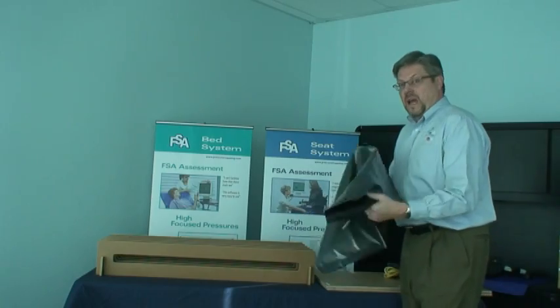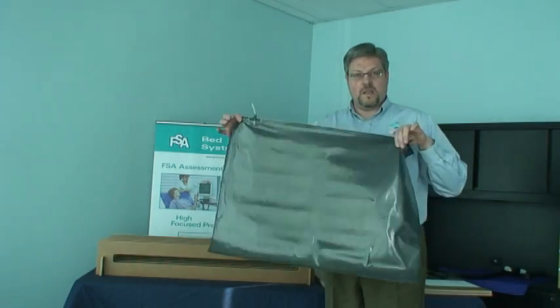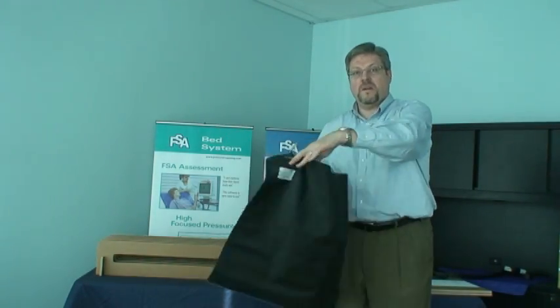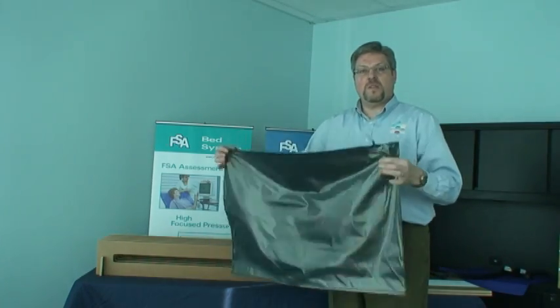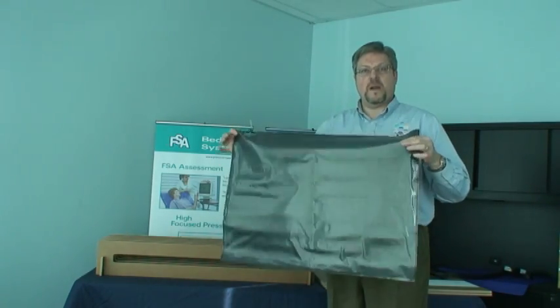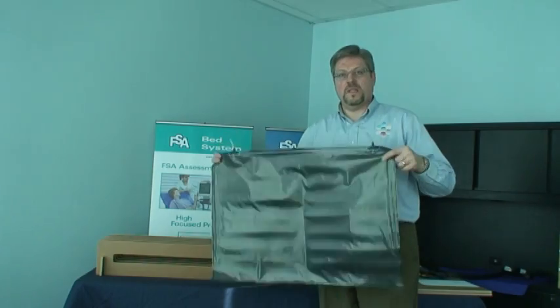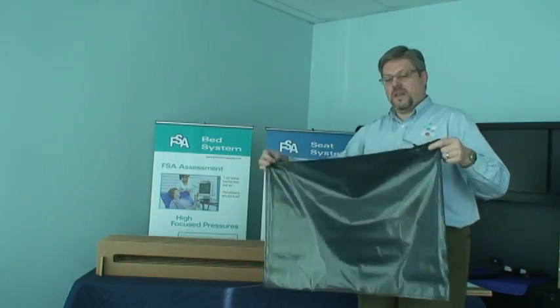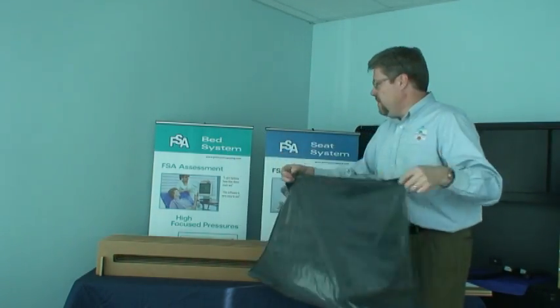You have a calibration bladder. You can see it's clear on one side, black on the other. Makes it very easy to understand. You want to make sure you put the clear side, which is softer and more flexible, down on top of the sensing mat. We'll get to building the calibration sandwich, so to speak, in just a minute.